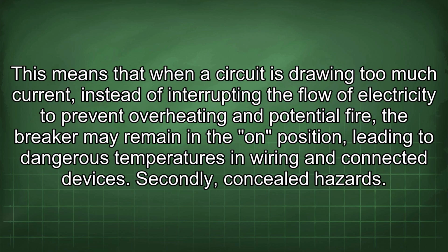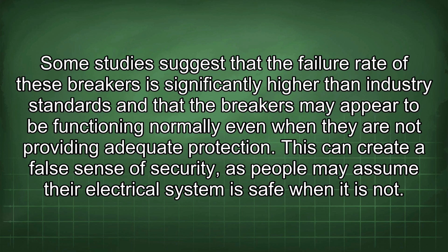This means that when a circuit is drawing too much current, instead of interrupting the flow of electricity to prevent overheating and potential fire, the breaker may remain in the on position, leading to dangerous temperatures in wiring and connected devices. Secondly, concealed hazards. Some studies suggest that the failure rate of these breakers is significantly higher than industry standards and that the breakers may appear to be functioning normally even when they are not providing adequate protection.